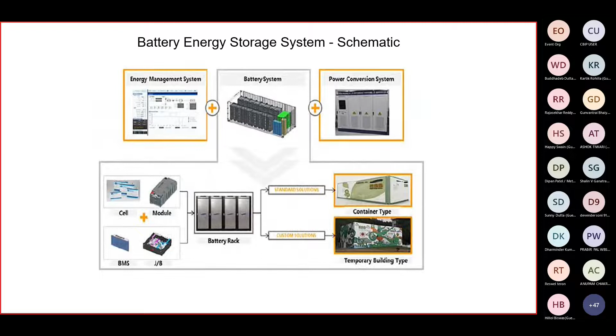In case of BRPL, we have recently deployed 6 battery energy storage systems at the LV side of the distribution transformer, 11 kV by 415. We have used lithium iron phosphate based energy storage, a chemistry that is thermally stable compared to NMC and other chemistries. In terms of installation, we designed and used separate enclosures for the battery bank, PCS, and an ACDB, which includes the energy management system.